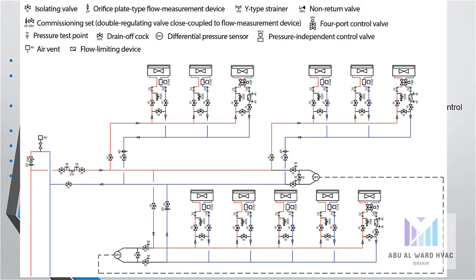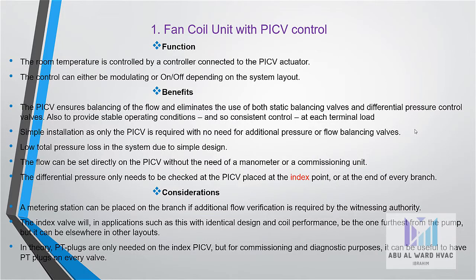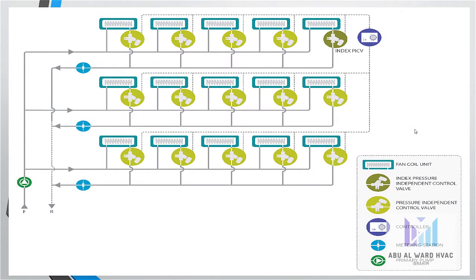of every branch. Considerations: a metering station can be placed on the branch if additional flow verification is required by the witnessing authority. The index valve, in applications such as this with identical design and coil performance, will be the one furthest from the pump, but it can be elsewhere in other layouts. In theory, PT plugs are only needed in the index PICV, but for commissioning and diagnostic purposes, it can be useful to have PT plugs on every valve. Here is the schematic diagram for the PICV and the fan coil unit applications.